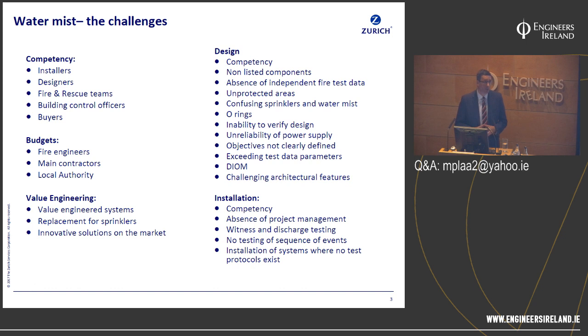But fire engineers, in my experience, do lack the competency and knowledge to adequately understand the scope and use of water mist. Only recently I had a fire engineer from a very well-known consultancy recommend in my presence water mist for a 25-metre tall warehouse containing hanging garments. And there is no such test protocol for such application. And it was on a wing and a prayer that particular consultant suggested to me that actually this would be a good solution instead of sprinklers. And so we have to be careful. It is a specific application solution. We have fire engineers, fire consultants out there recommending water mist, but remember it needs to be backed up by independent test data for the application in which it's going to be used. And I'll cover that in a bit more detail.